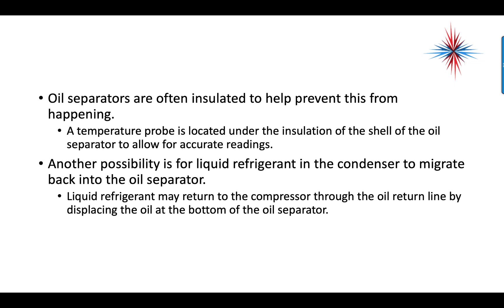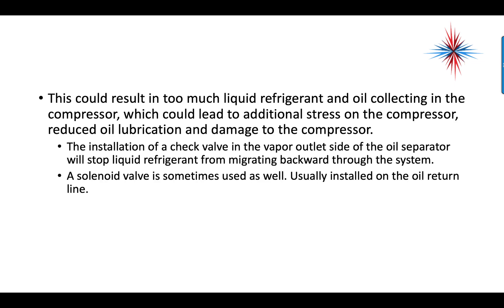We have to remember the compressor does not like liquid. This could result in too much liquid refrigerant and oil collecting in the compressor, which could lead to additional stress on the compressor, reduced lubrication, and damage to the compressor. The installation of a check valve in the vapor outlet side of the oil separator will stop liquid refrigerant from migrating backward through the system.